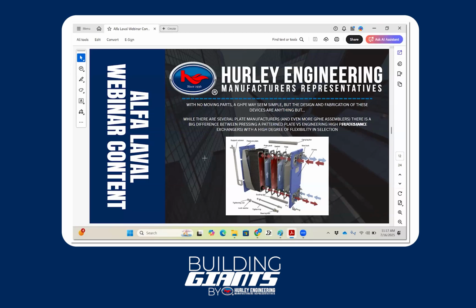Yep. So again, it seems pretty simple because there's no moving parts, but to do them properly, design them properly, and fabricate them in a way that it's serviceable is anything but simple. There are several plate manufacturers and even more gasket plate heat exchanger assemblers, but there's a big difference between pressing patterns versus having a high performance exchanger with a high degree of flexibility.